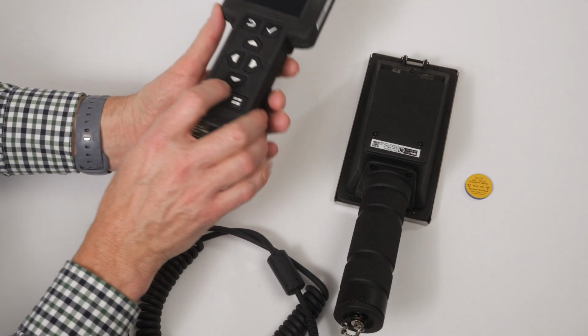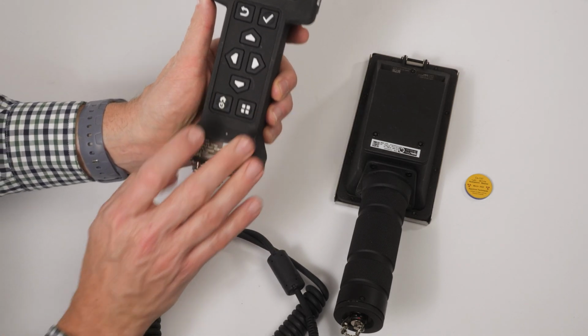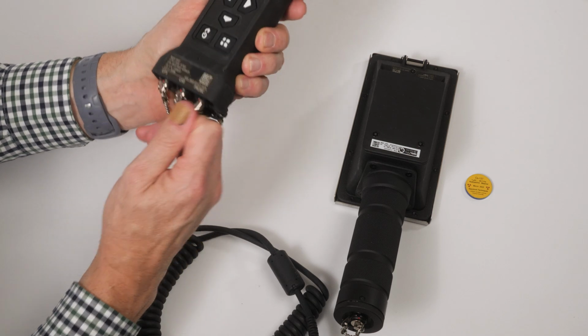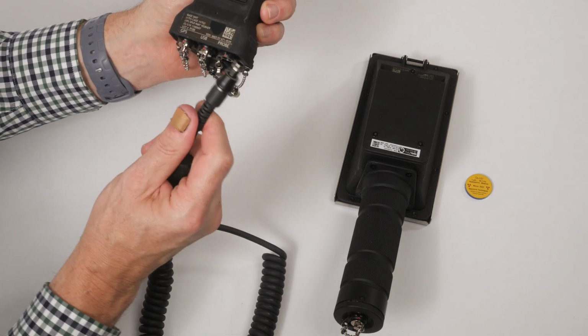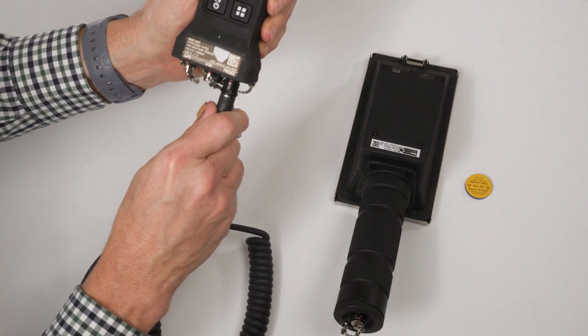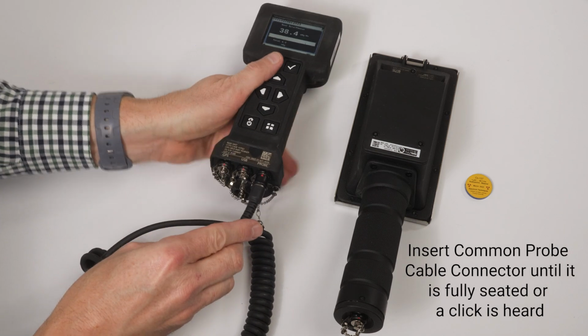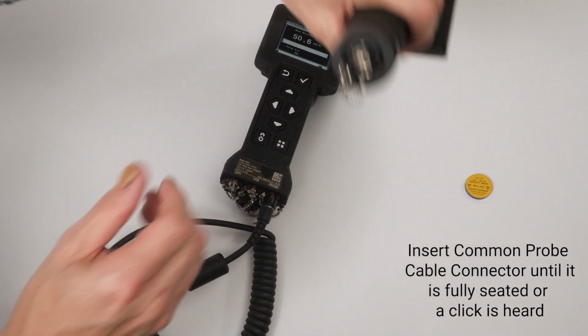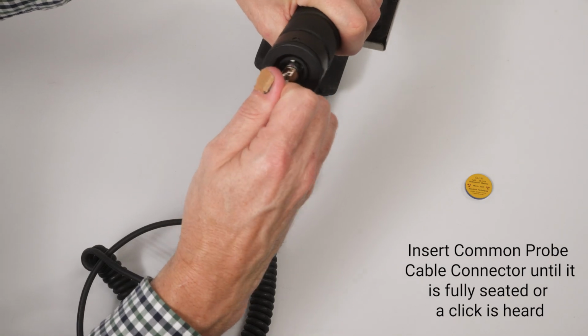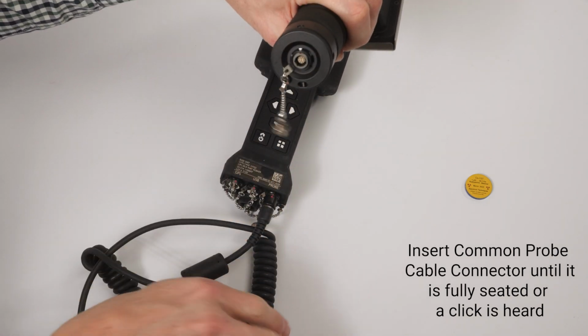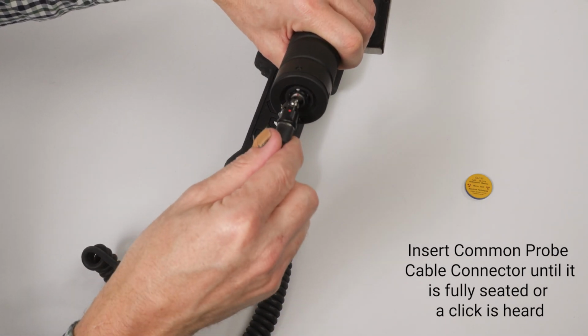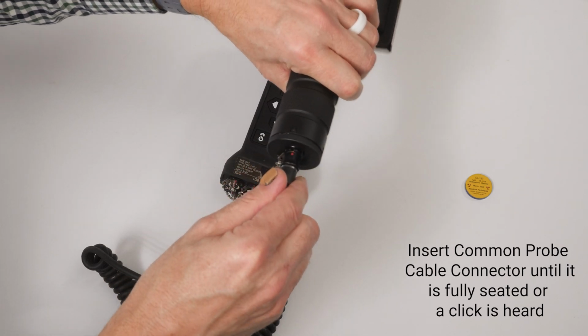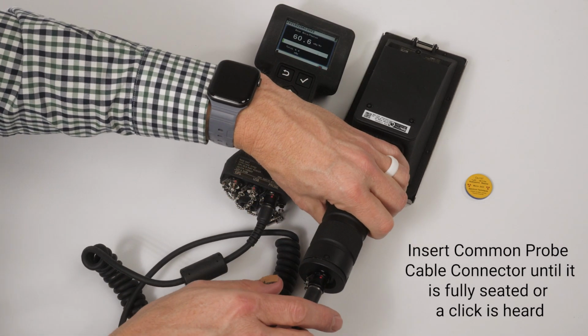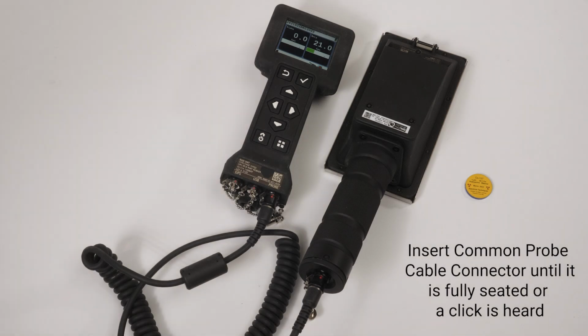To place the alpha-beta probe in operation, power on the base unit. Remove the probe connector protective cap from the base unit and connect the common probe cable connector to the probe connector on the base unit, inserting the cable connector until you hear an audible click. Then, with the other end, you'll attach it to the alpha-beta probe. First, remove the protective cap, then insert the connector, aligning the red dots until an audible click is heard.